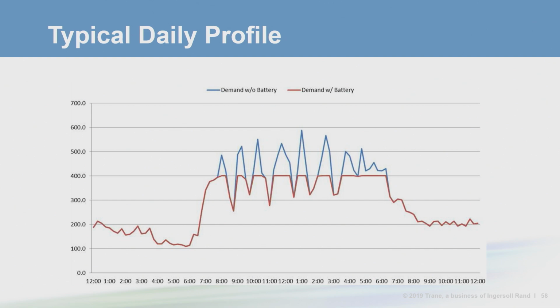When the load spikes, the battery discharges, and as the load drops, the battery charges. For example, instead of 6 batteries staying in discharge during the cooling cycle, 3 batteries can take turns charging and discharging during the same cycle.